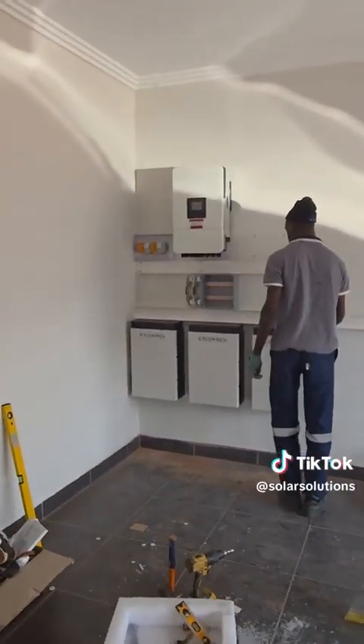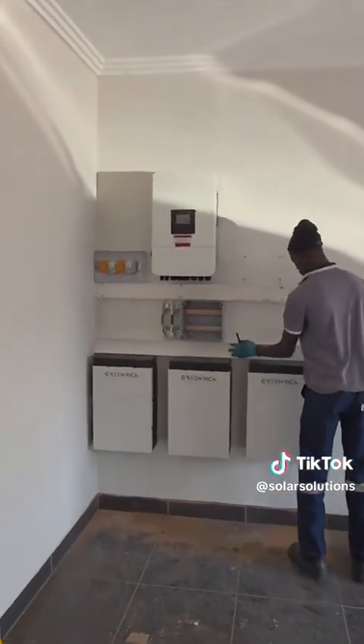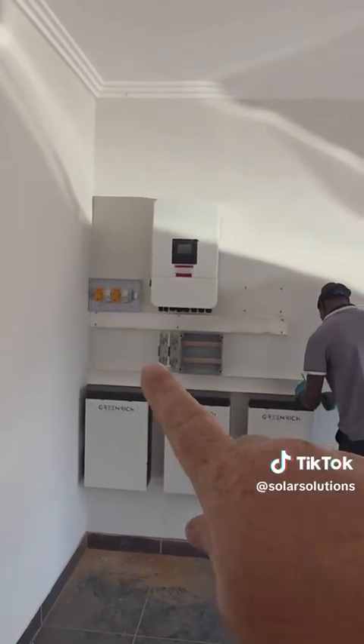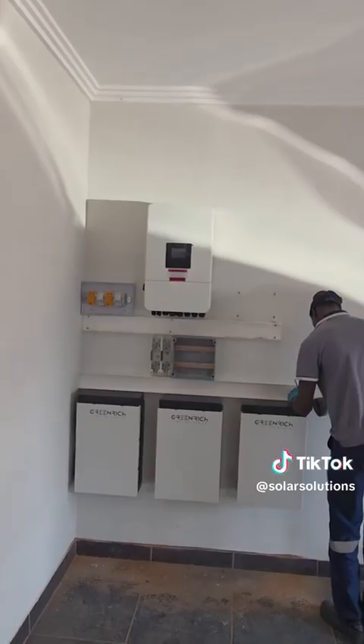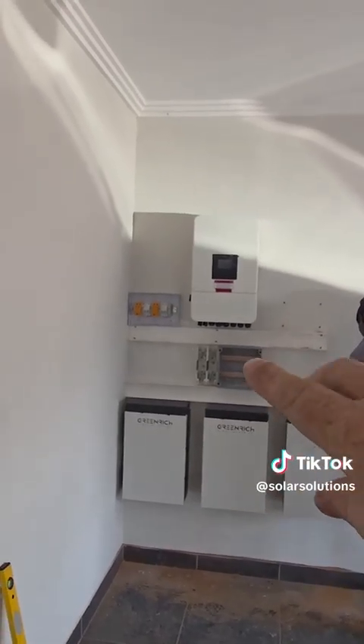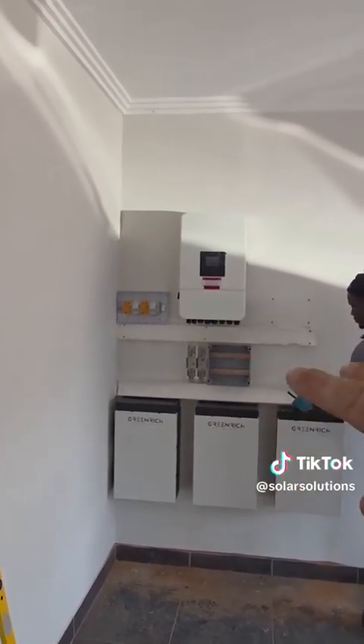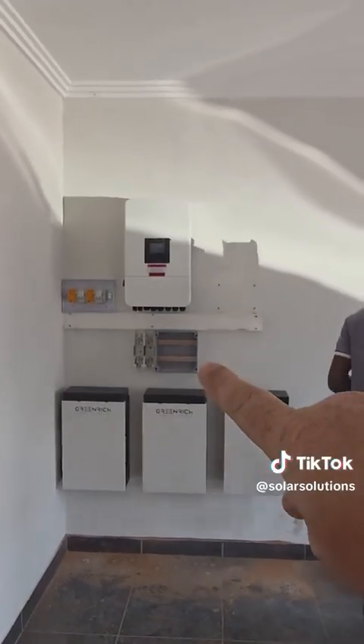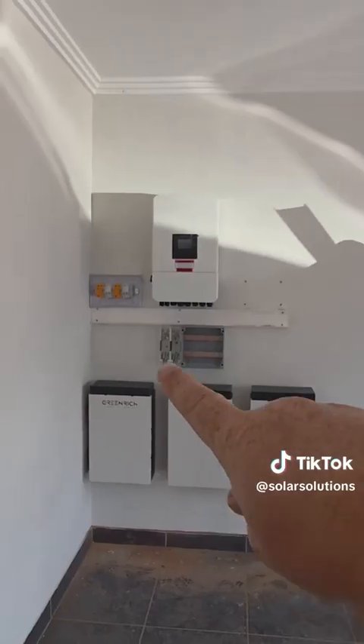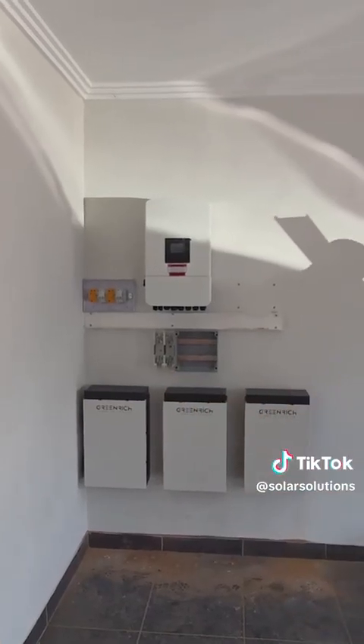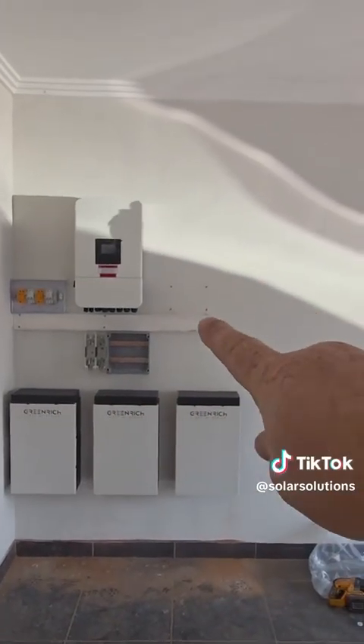Ford is busy mounting all the inverters and batteries. We've got the inverter mounted about 500mm from the left hand side of the wall, and our DC combiner, which has 2 strings in it with surge protection fuses and a breaker. We've got the bus bar for the battery cables, and from the bus bar it goes through a 250 amp battery disconnect into the inverter, and our AC DB is going to go here.